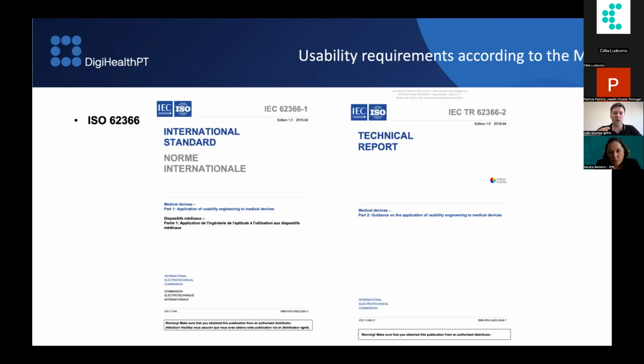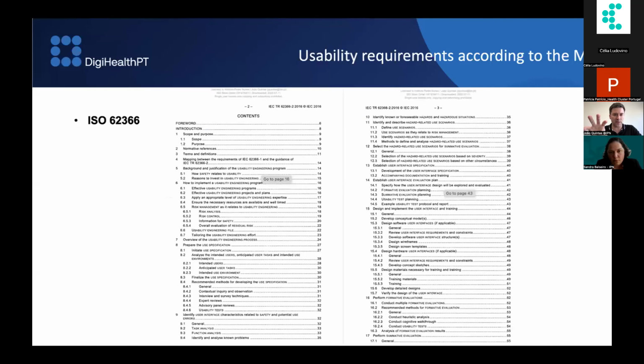And in part two is where you really have the guidelines on how to perform this work. So basically, focusing on this second part, you will see a lot of boxes again, okay? One of the very specific things that you will need to take care of regarding usability in medical devices is that this is essentially a risk and hazard oriented approach, okay? Instead of "my users like it very much, it's very easy to use," in this case you will need to show that it's usable in the sense that it's not dangerous and it will not lead the user to do wrong things if they are not careful enough.